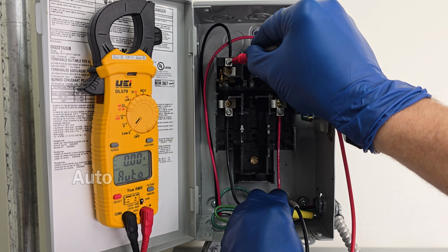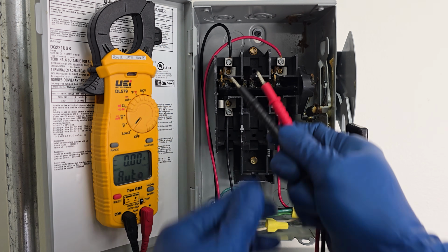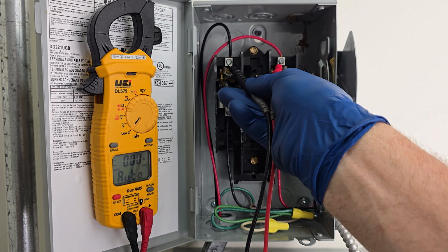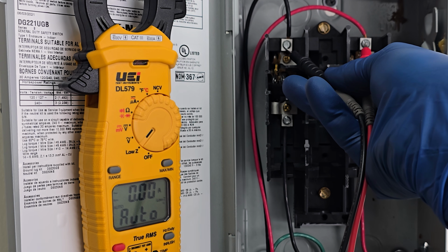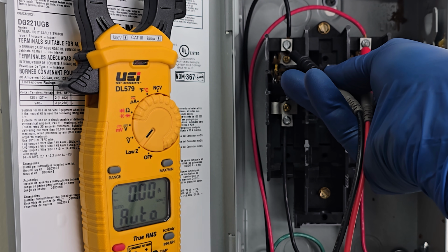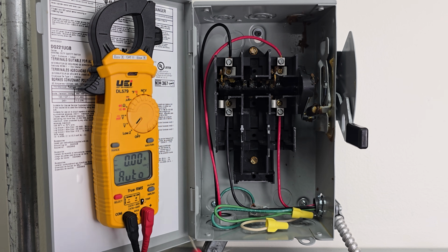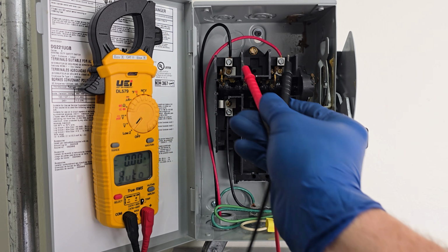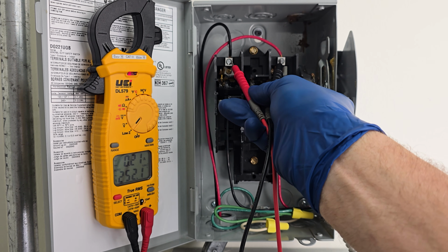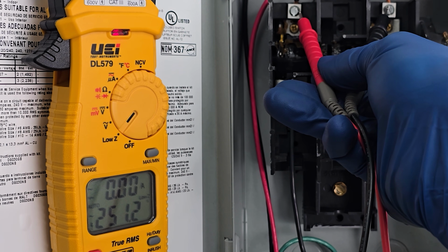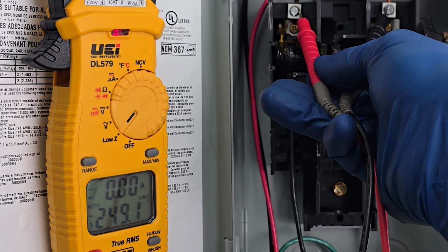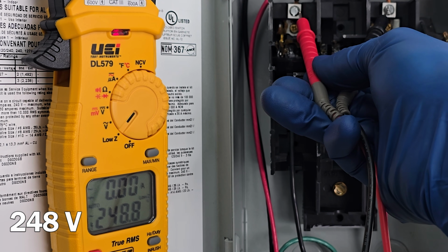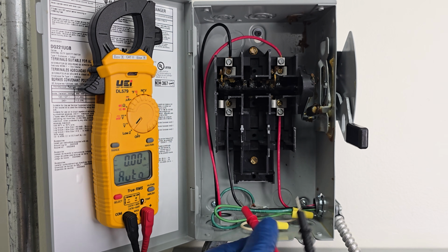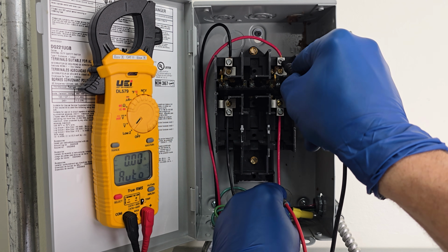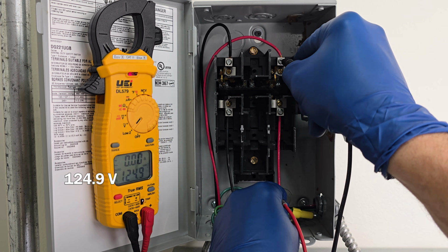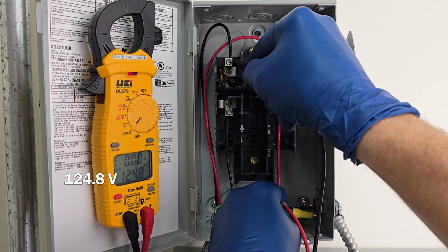And you can see down at the bottom it just says auto. And so it's not changing, it's not measuring any voltage. So it just says auto. Now I'm going to turn the power back on. I'm going to leave it on the low Z, and we'll measure the voltage then. So now we have voltage, and so let's measure between these 2 points. And you see we were measuring 250, let's see here. All right, 248 volts. And then if we were to measure between the ground and each one of these, you see we're measuring 124.9 and 124.8.